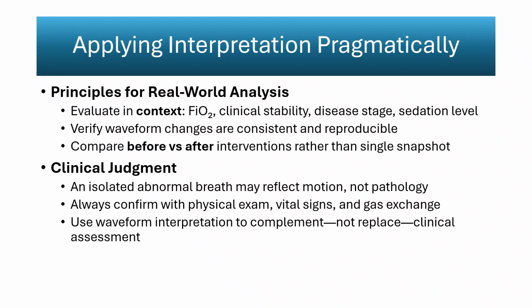Interpreting graphics in real clinical settings requires attention to context rather than isolated waveform features. A waveform must always be evaluated alongside the infant's fractional inspired oxygen requirement, overall stability, disease trajectory, and the degree of sedation or spontaneous activity. These factors influence both the shape of the breath and the variability between breaths. Before drawing conclusions, confirm that the observed pattern persists across several cycles and is not a transient artifact. Comparing graphics before and after an intervention provides a more reliable signal than interpreting a single breath in isolation.